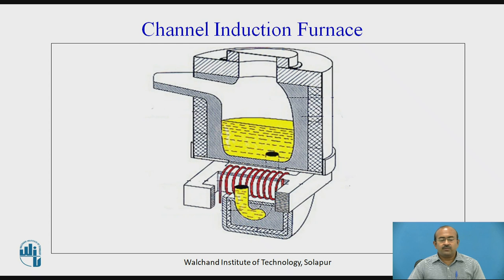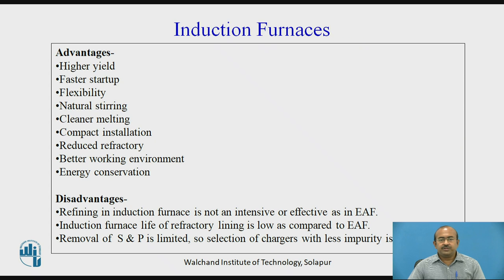Overall advantages of induction furnaces include higher yield, faster startup, flexibility, natural stirring, cleaner melting, compact installation, and reduced refractory consumption. Disadvantages include: refining in induction furnaces is not as intensive or effective as in electric arc furnaces; the life of the refractory lining is lower compared to electric arc furnaces; removal of impurities is limited, so selection of charge materials with less impurity is necessary.